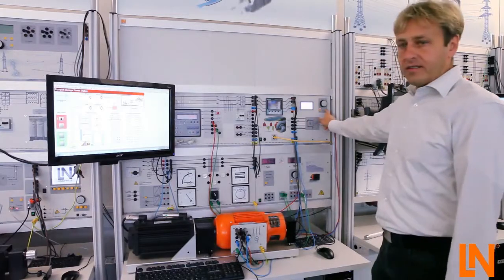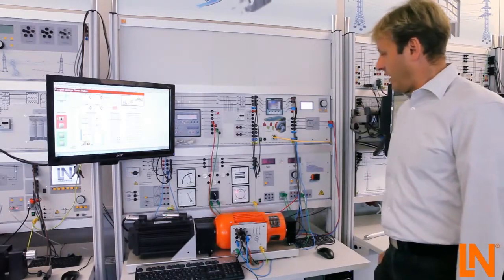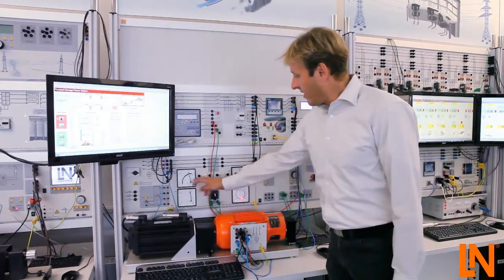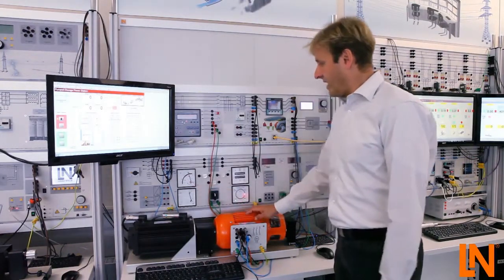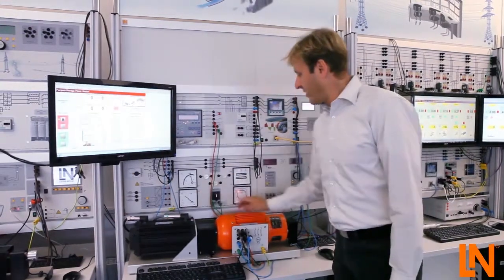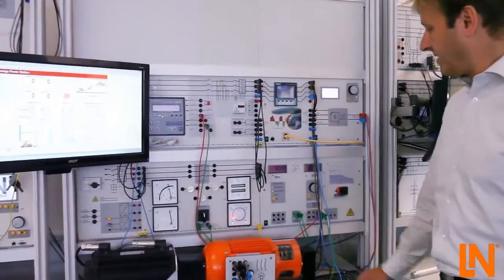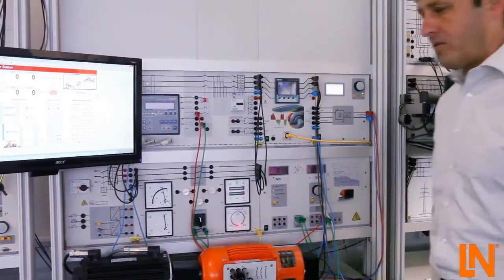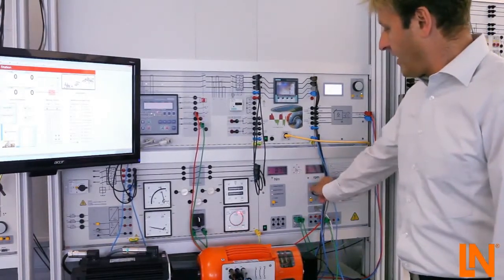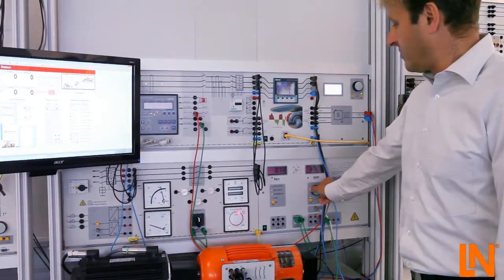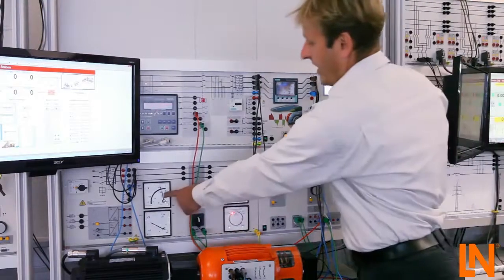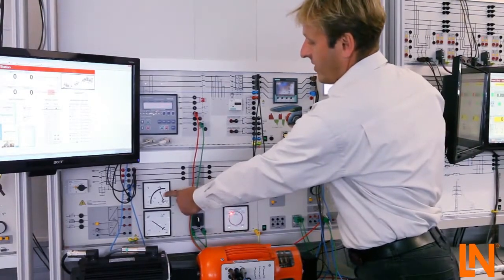Then I switch on the exciter voltage, and you see now here the synchronization unit where you can see the voltages of the generator and the mains, as well the frequency, as well the difference between the voltages of generator and mains, and the synchronous scope for better seeing how the angle is. So now I have to synchronize by changing the speed, and I have to control the voltage of the generator by changing the exciter voltage.